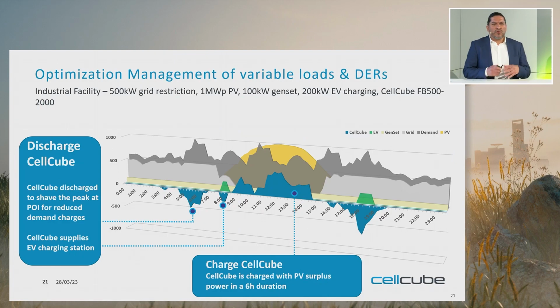Another case is when you have a grid restriction of 500 - that means you cannot take everything from the grid, even if it's cheap, because you don't have enough connection lines. But you will have a good portion of PV installed, and the surplus of the PV will charge our battery, so that we make kilowatt hours during the times when the solar is not producing. We discharge, firming the solar energy, time-shifting the solar energy fully.